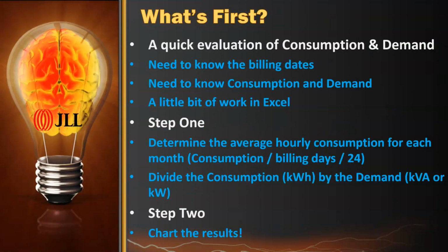We'll talk about where they come from and how they're generated, but for now I just want to talk about what's the first thing you do. If I was looking at a facility, the first thing I would do is say, I want to see your utility bill, and I want billing dates, and I want to know the consumption and the demand. I'm going to do a little bit of work in Excel to determine something called load factor. Load factor is the average hourly consumption for each month. I take the consumption for that month, divide it by the billing days in that billing period, and divide it by 24 hours in a day. Then I divide that number by the demand for the month, kVA demand or kW demand.